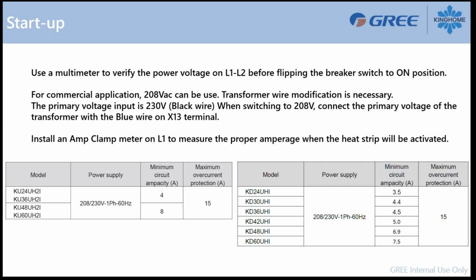The system will run, for example, if you have 208 in your application but you forgot to switch the wire from the black wire to the blue wire on the transformer, but that will result in maybe only 21 or 22 volts from the transformer. So you will not have a proper 24 volts coming out of it. That will not break the system or fry the board or anything like this, but you won't have 24 volts at the output.